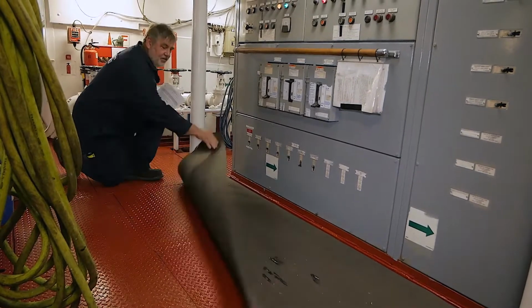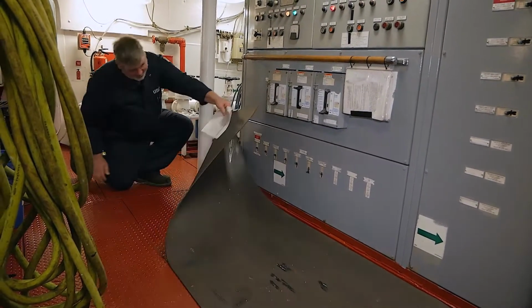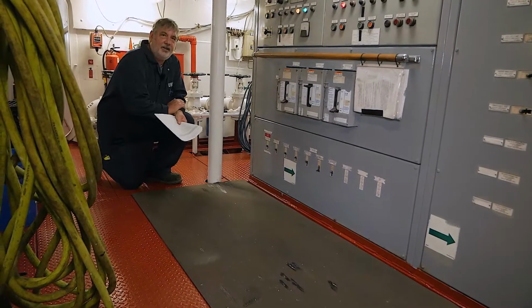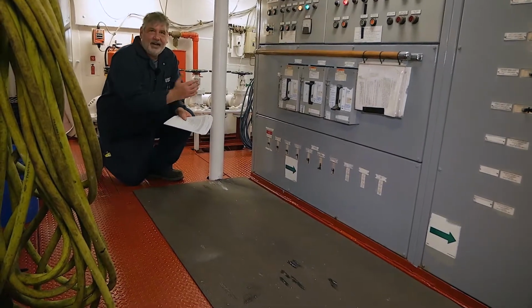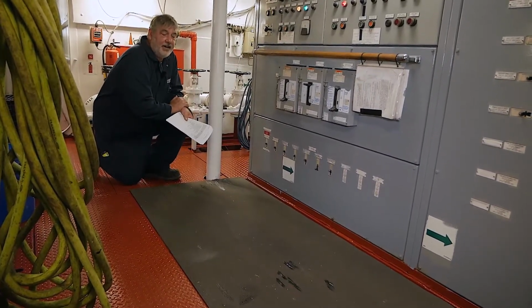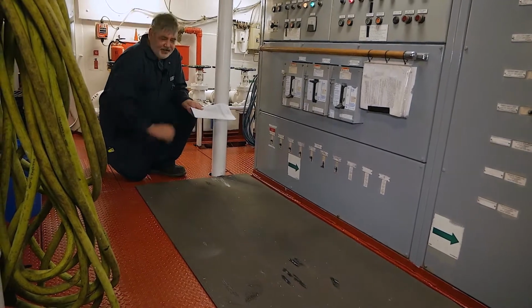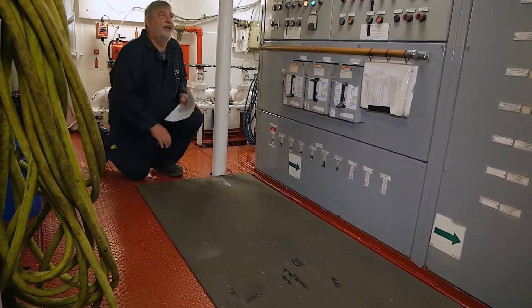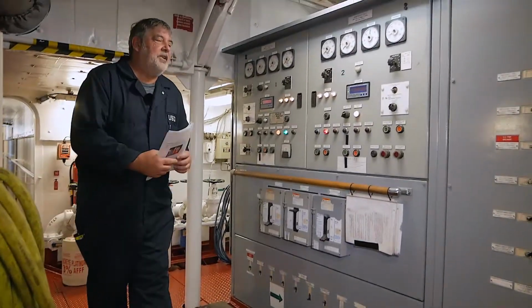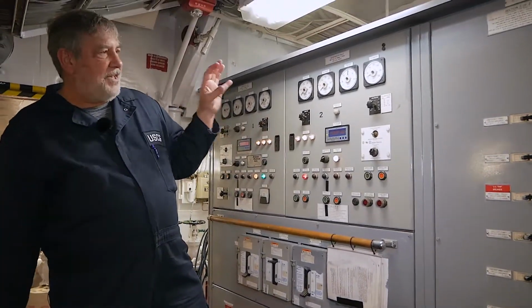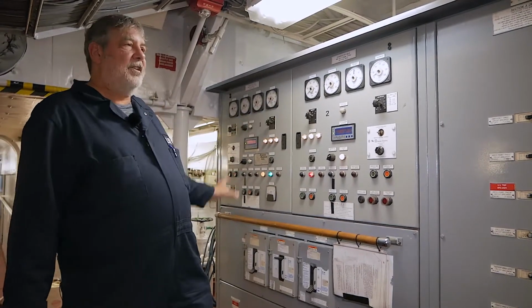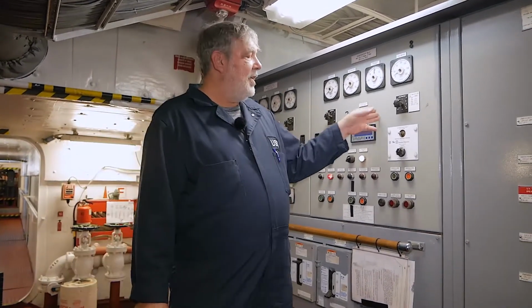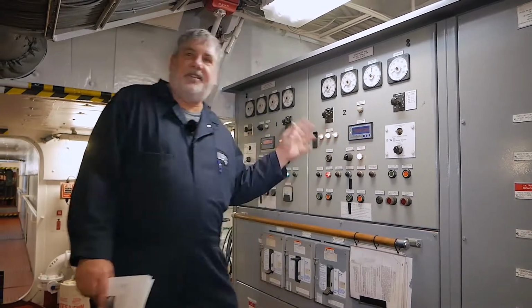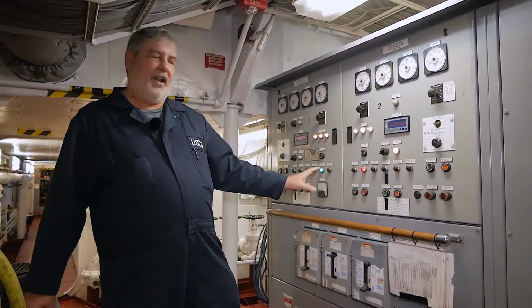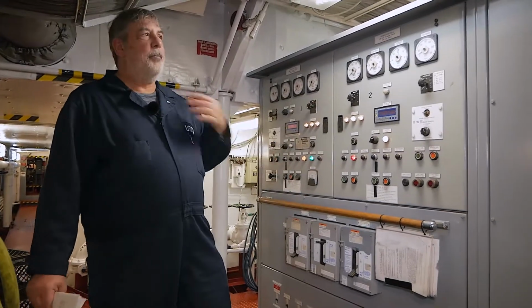Some matting you can turn up and you will see specification data verifying that it is electrical grade. Other times it may not, but you can verify if it's electrical grade matting or not. This is electrical grade matting. One of the biggest safety features of a switchboard is that they are enclosed. There's no place on here where someone could accidentally reach into it and get themselves shocked. No openings are allowed, and as you can see, there are no openings on this one.